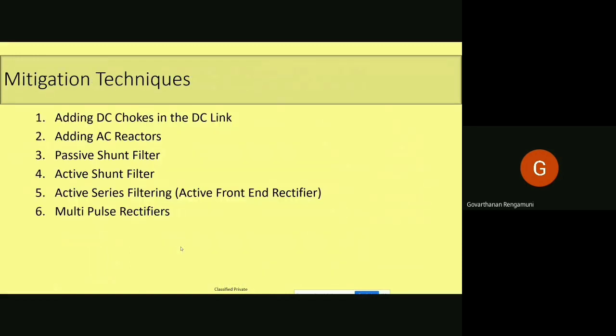into different mitigation techniques. There are 6 mitigation techniques available that are commonly used, and we are going to discuss them today. The first one is adding DC chokes in the DC link. Second, adding AC reactors. Third is the passive shunt filter. Fourth is the active shunt filter. Fifth is active series filtering, otherwise called the active front-end rectifier. The sixth one is the multipulse rectifier. All these mitigation techniques are listed considering a three-phase rectifier only, meaning the VFD 6 pulse rectifier. We can see them one by one.